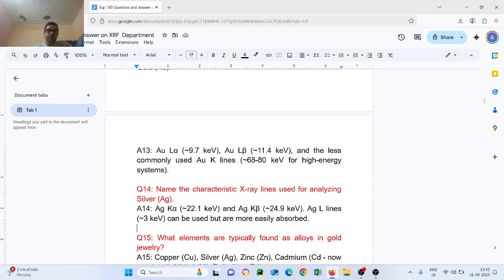Question number 14. Name the characteristic X-ray line used for analyzing silver, Ag. Ag K alpha 22.1 keV and Ag K beta 24.9 keV. Ag L lines, around 3 keV, can be used but are more easily absorbed.